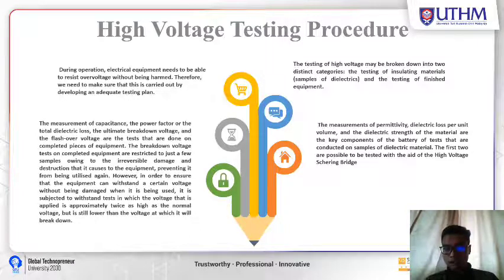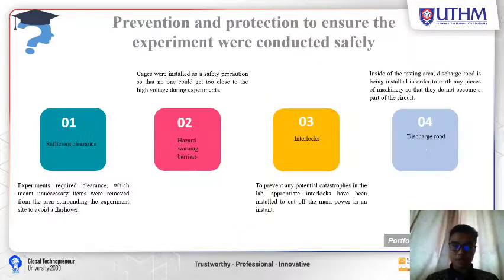The first two are possible to be tested with the aid of the High Voltage Schering Bridge. Okay, next is prevention and protection to ensure the experiment will conduct safely. First is sufficient clearance. The experiment required clearance, which means unnecessary items were removed from the area surrounding the experiment site to avoid a flashover. Two is hazard warning barriers.